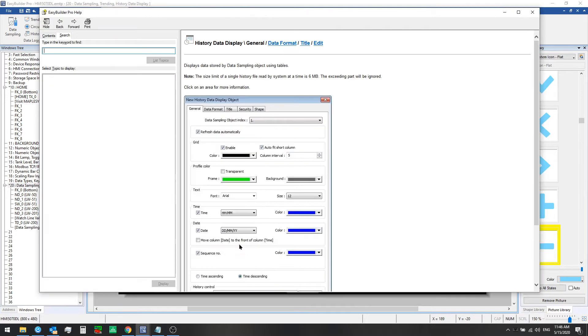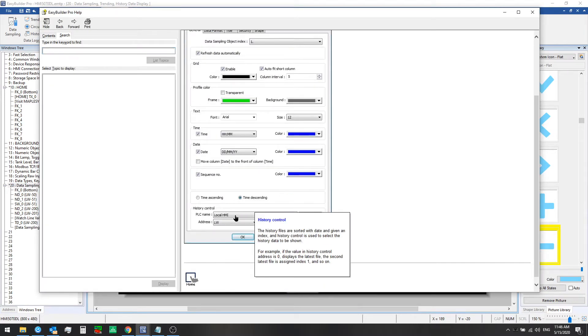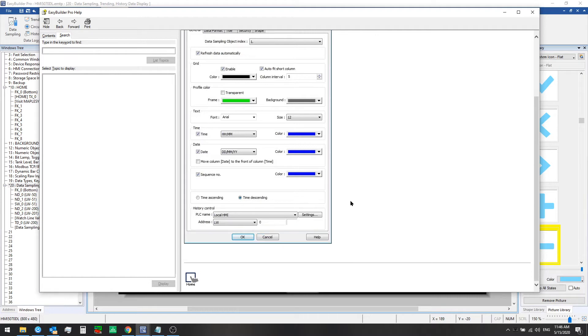If we hit F1 on our keyboards we can pull up the help menu and click on this option. What it says here is that if we enter a zero into the designated history control register it will show the data for the current date. If we enter a 1 it will show yesterday's data, a 2 will be the day before, and so on. How many days worth of data you can show with the history data display is dependent on how you set up your data sampling object to begin with.